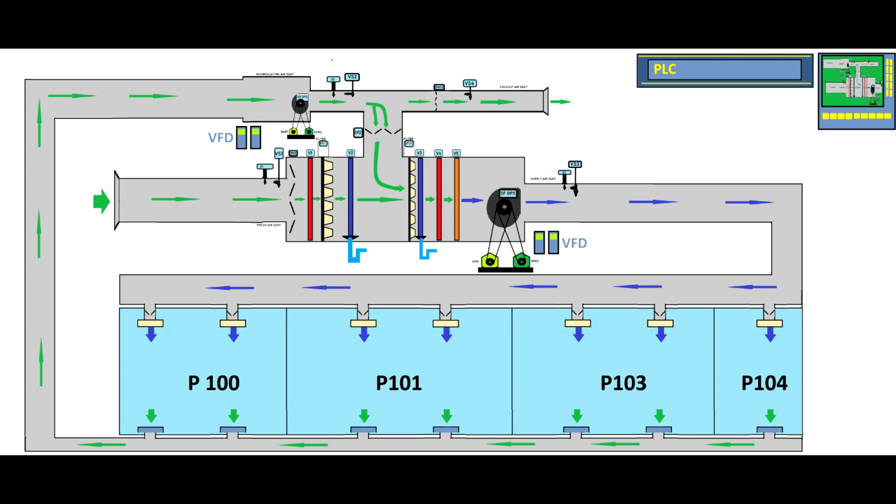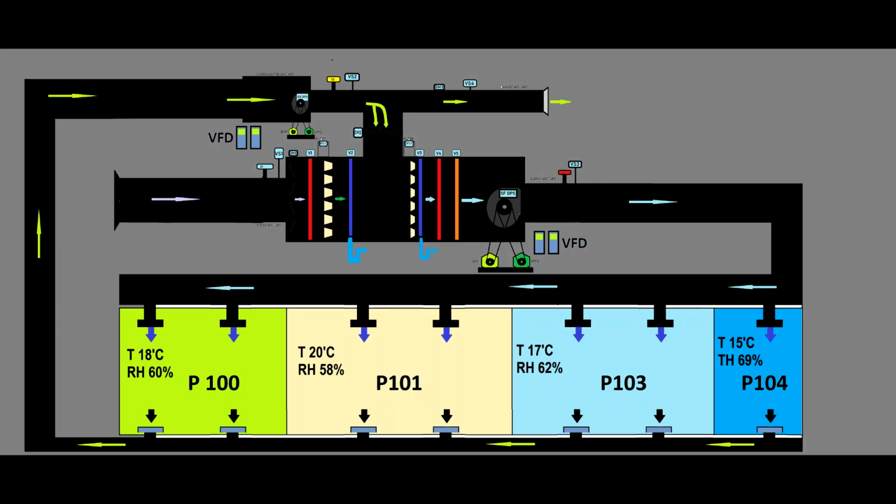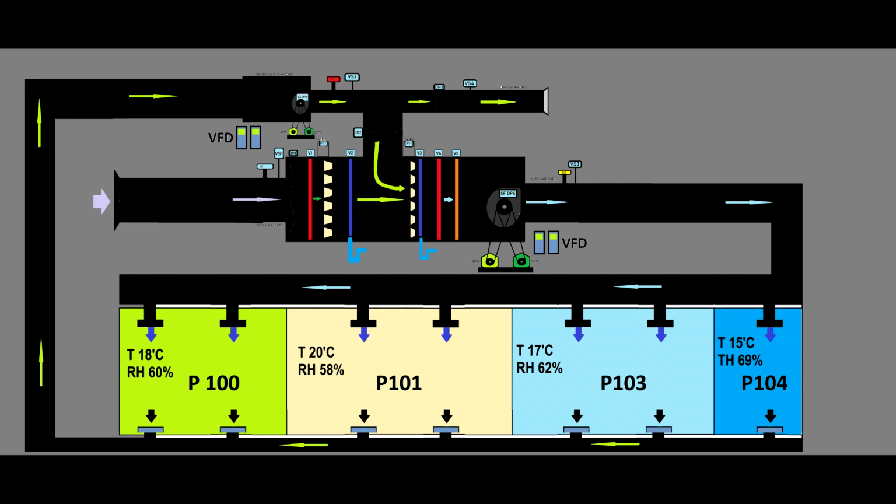The global air will be shared between these rooms, and if I need different temperatures in each room, that will not be possible. This is a perfect example of a poor design system.